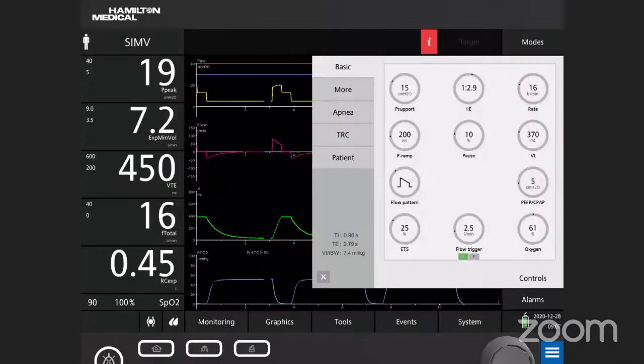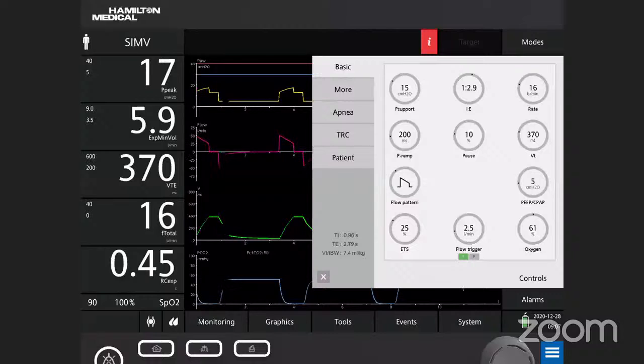Similarly, you will set the pause time. It's a volume control mode of ventilation, so you will set the pause time so that we know the plateau pressure as well as the peak inspiratory pressure. And again, because you have added pressure support, you will have to set the pressure support variables. That is, what is the pressure support level that you would like? What is the inspiratory rise time that you would like? And again, I had mentioned the expiratory trigger sensitivity.